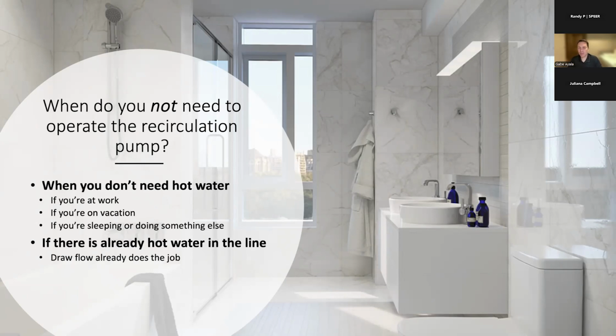Secondly, if there's already hot water in the line, the pump doesn't need to run, because once hot water is at the end of the plumbing terminal and it's just flowing out of your faucet, then the draw flow, the city pressure, moves the hot water through your pipes. So it's really only during this transitional period when your hot water lines have cooled down and there's a demand for hot water. That's really the only time that the pump needs to run. And then it only needs to run for about 30 to 60 seconds before turning off.